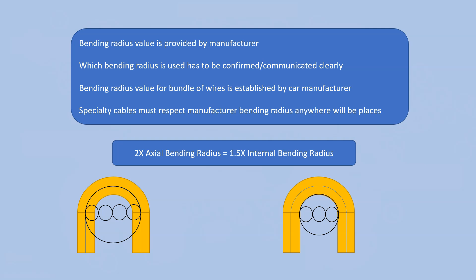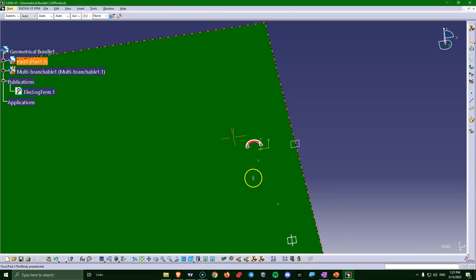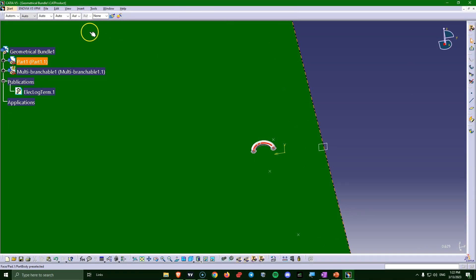Bending radius is not a fixed science or a fixed formula — you need to take every wire or cable and verify that your design respects exactly what the datasheets specify. This is what it means to be an electrical harness CAD designer: it's not only about CATIA V5, but about accommodating all the parameters and requirements coming from reality. Now let's take a look in CATIA V5 as an example.